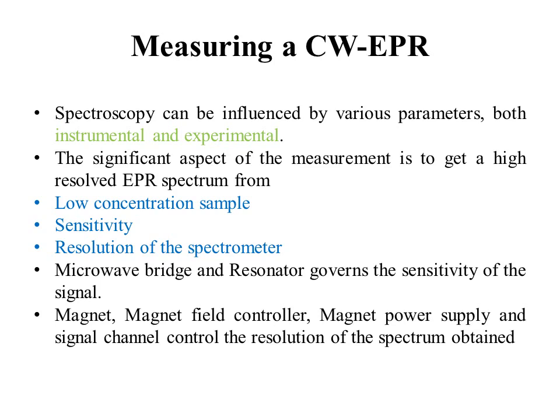The microwave bridge and resonator govern the sensitivity of the signal. The magnet, magnetic field control, magnetic power supply, and signal channel control the resolution of the spectrum obtained.